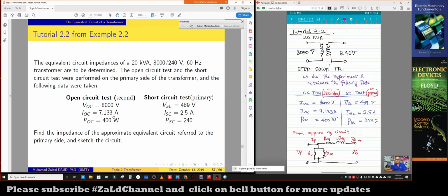So as you can see here, as explained earlier, in the open circuit test, basically we supply the full line voltage. Full line voltage means the full voltage that is at the primary side, which is 8000 in this case.